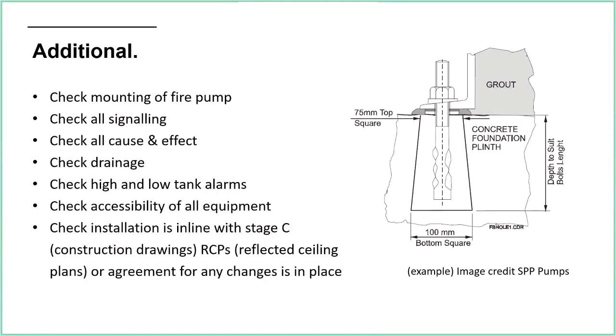Check the installation is in line with stage 3, so construction drawings. RCPs, reflected ceiling plan. So that's what you'll be looking at to check the position of the sprinkler heads. You'll be staring up at the ceiling, and you've got a drawing that is basically exactly that. It's looking up at the ceiling. So it's not from above looking down, it's from below looking up. Agreement for any changes in place. So it may well be that the sprinklers have not been installed to the stage 3 construction drawings, but if they're not, there should be some paperwork, some agreement in place to say, we found this problem and the instruction was given to move that pipe from here to here, or move that head from here to here. All of that paper trail should be in place to show any deviation from the stage 3 drawings.